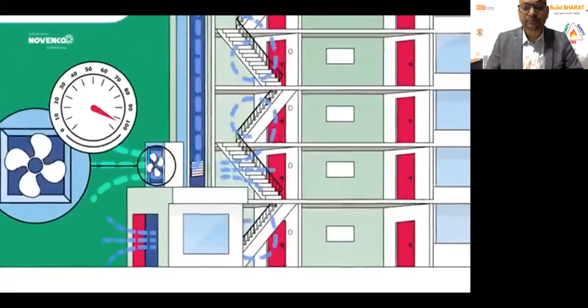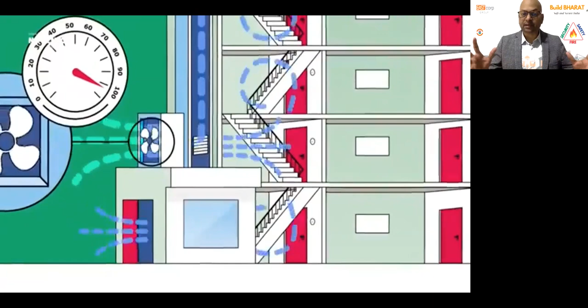And this is a final exit discharge. Again, there will be some loss of air because you are going to use that door to go out. Again, the differential pressure will take care of it. So it's a very engineered way. It has a variable differential fan drive, which will take care of those losses, and it will maintain that differential pressure of 50 Pascal throughout your evacuation time. Now the evacuation time can be 5 minutes, it can be 50 minutes. It doesn't have any rule.